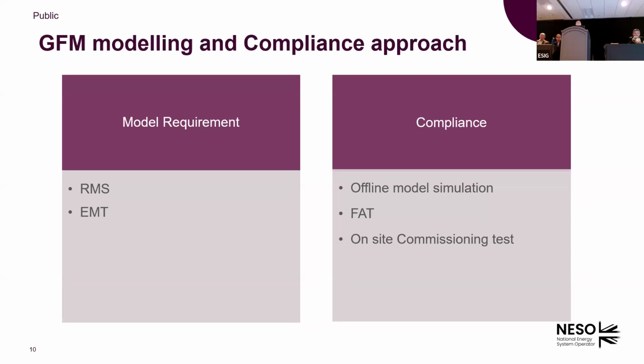However, we're putting a lot of emphasis on the site monitoring requirement as well. They have to keep monitoring the grid forming performance, especially when a relevant event happens in the system, like a RoCoF event or any oscillation event. For the model requirement, that's standard: they have to submit both an RMS model and an EMT model, which need to have a close alignment in performance between the two.